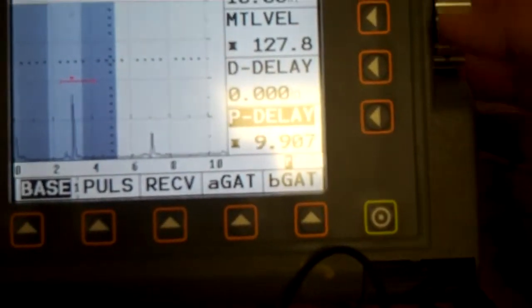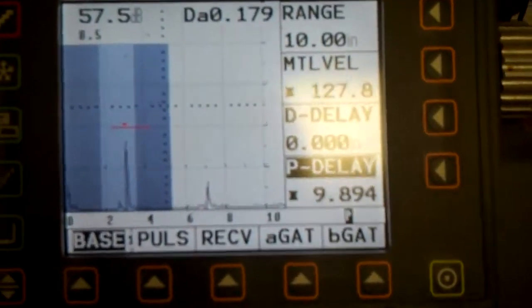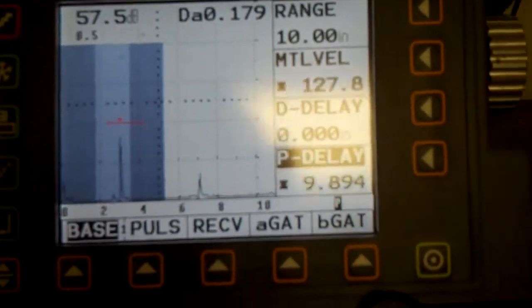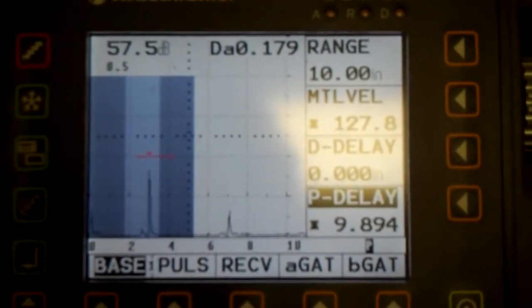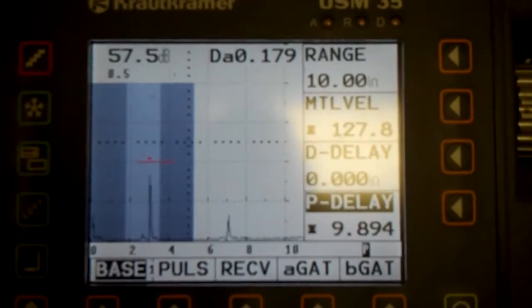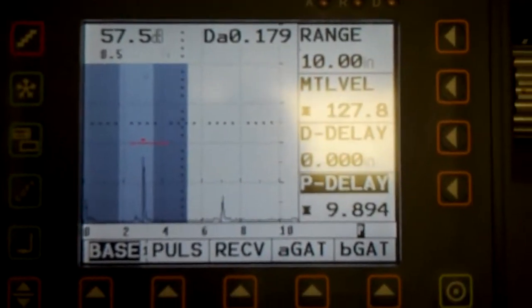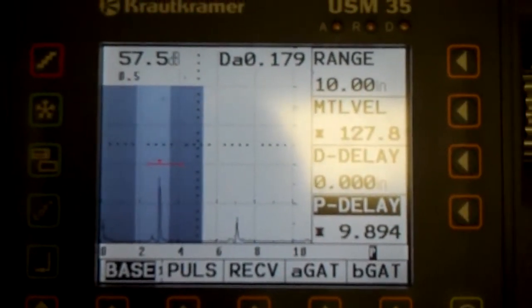Yeah, and then I'm going to back this up just a little bit. Okay, so now we're at 3 and 7. 0.127 on my velocity. 0.130 is technically what it's supposed to be, so I would call that good. My delay is fine. I have no problem there. Gain is good. Still showing a depth of 0.179.